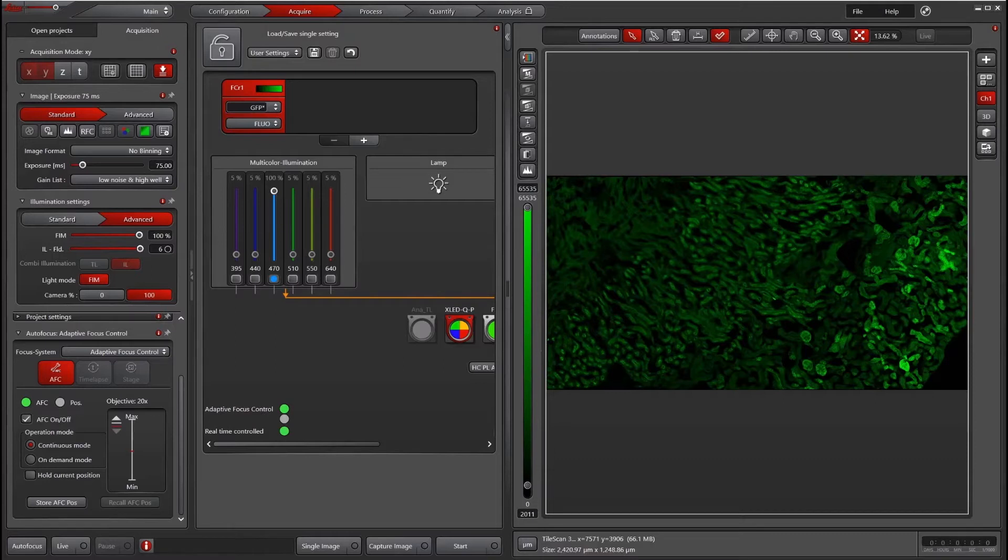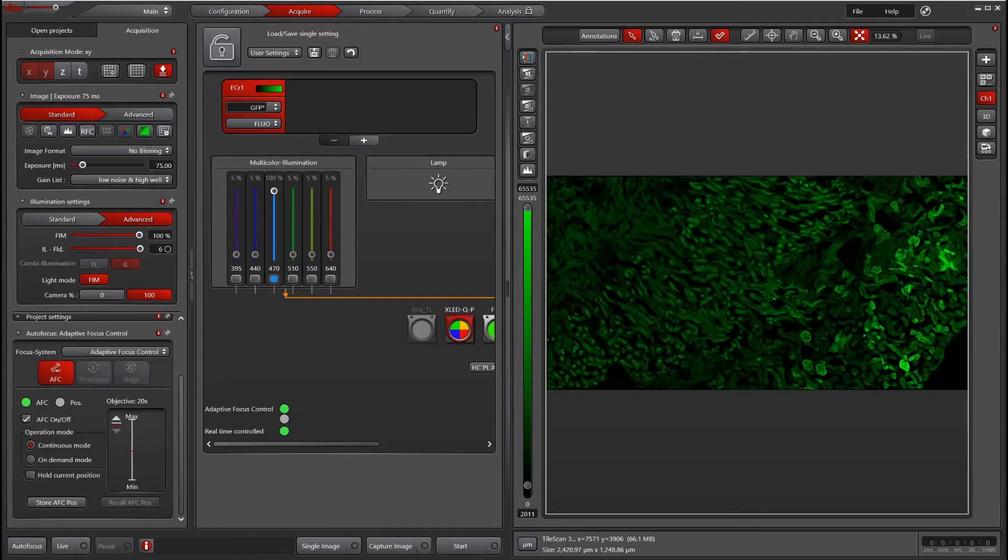AFC is a hardware autofocus mechanism that is available on DMI-8 microscopes. It works by sending an infrared beam up to your sample and looking for the difference in refractive index. It communicates with the motorized focus and adjusts the focus to the offset that is determined by the user.